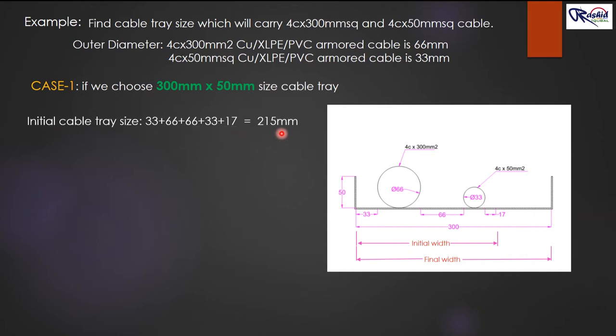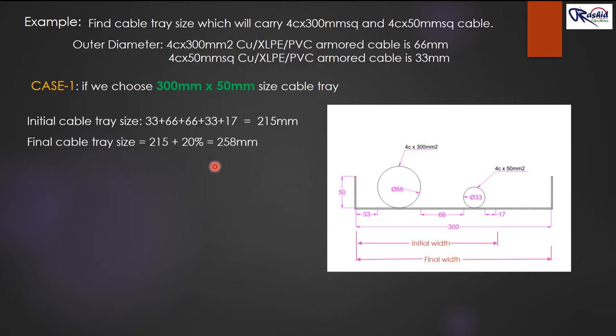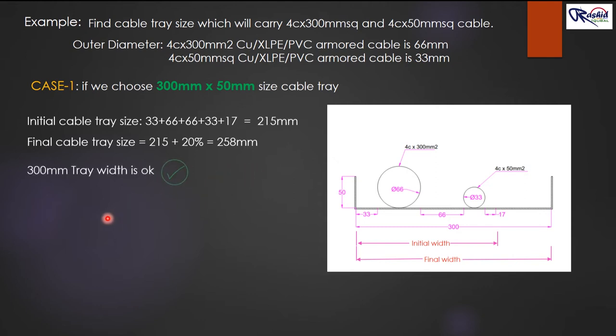Adding all initial values: 33 + 66 + 66 + 33 + 17 = 215 mm. Adding 20 percent extra: 215 + 20% = 258 mm. This width is not a standard market size, so we select the next bigger available size, which is 300 mm. Therefore, the 300 mm width is confirmed as acceptable.